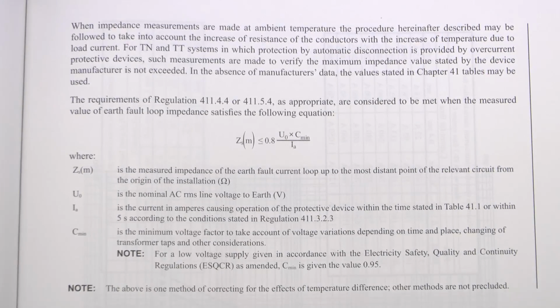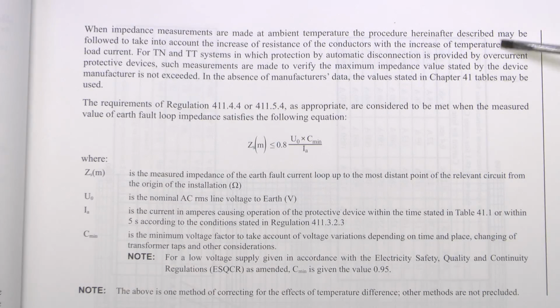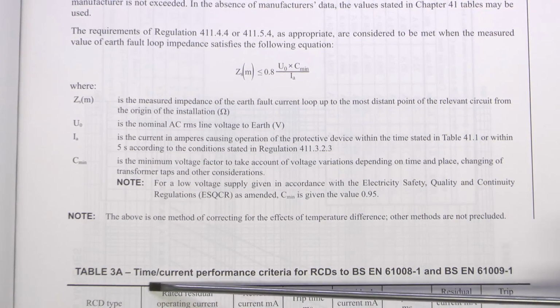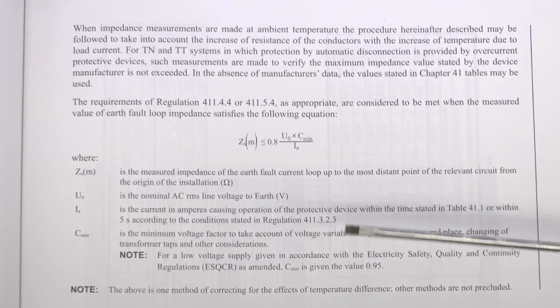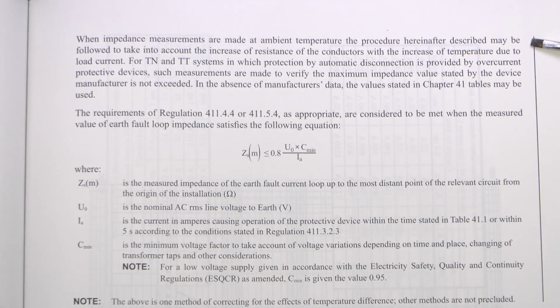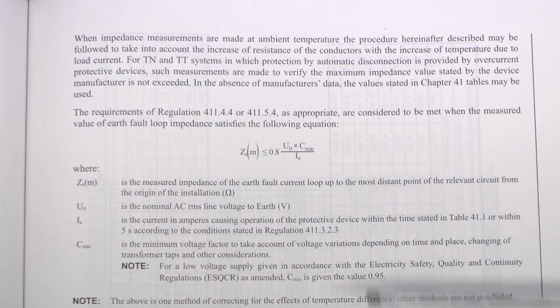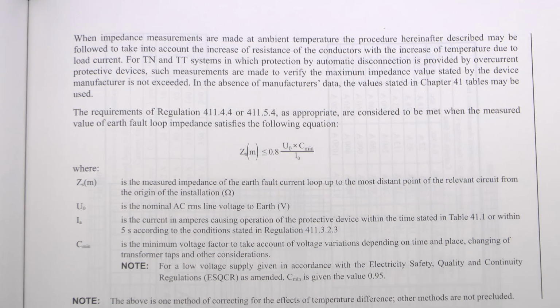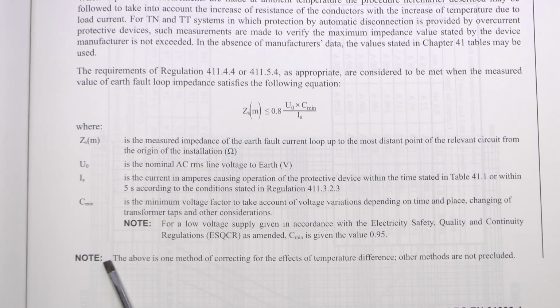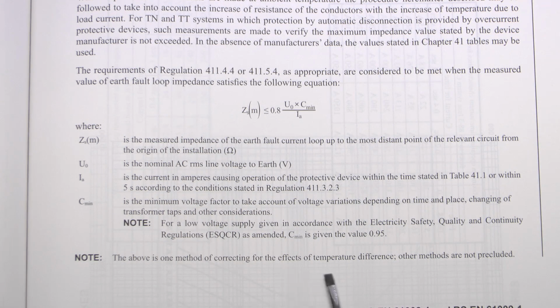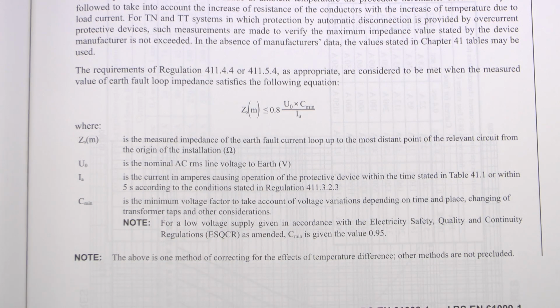The other part that's been considerably added is the section above table 3A with the time and current performance criteria. All of this is new, with various suggestions on impedance measurements, ambient temperature, other regulations referred to, and a value formula installed there as well. At the bottom there's a note which kind of makes the whole thing pointless: the above is one method of correcting for the effects of temperature difference - other methods are not precluded, so it's just one example you could use.